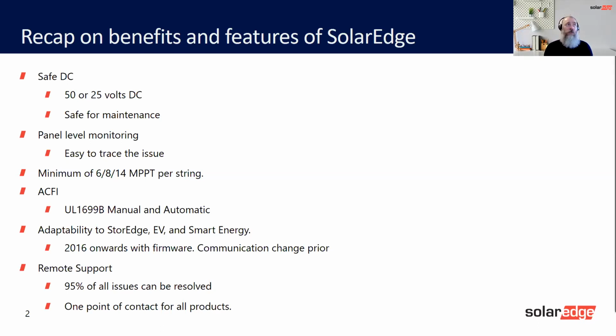So having arc fault circuit interrupter or arc detection that you see other inverters have, other manufacturers have, is great, but you must have a way of controlling that current. And the only products out there, which is the SolarEdge optimizer, the power optimizer, this controls the current and reduces it from 14 to 15 amps, which we tend to run, down to 300 to 200 milliamps, as I said.